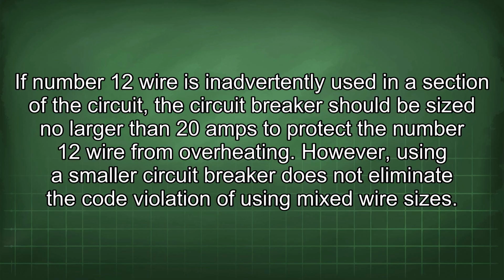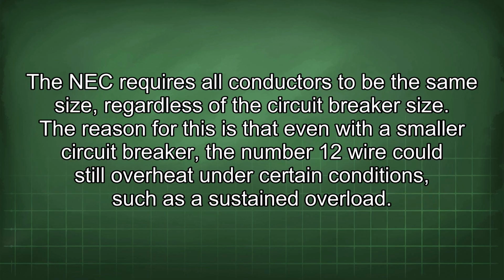However, using a smaller circuit breaker does not eliminate the code violation of using mixed wire sizes. The NEC requires all conductors to be the same size, regardless of the circuit breaker size. The reason for this is that even with a smaller circuit breaker, the number 12 wire could still overheat under certain conditions, such as a sustained overload.